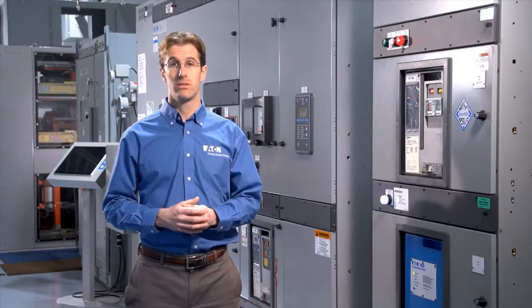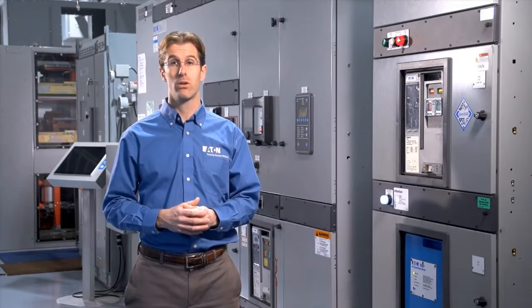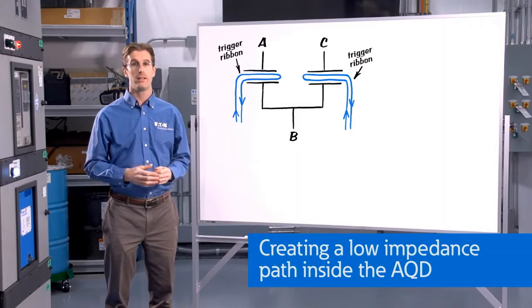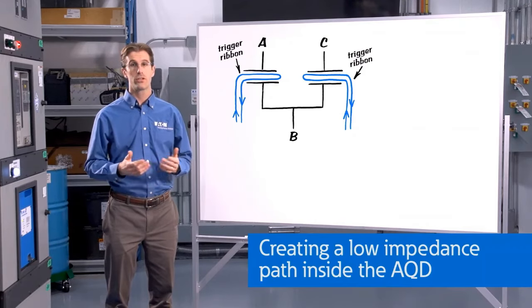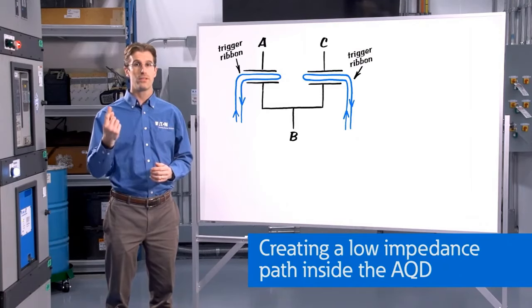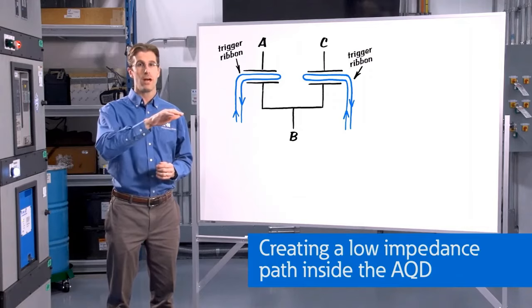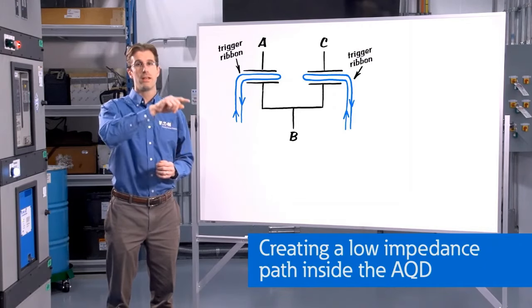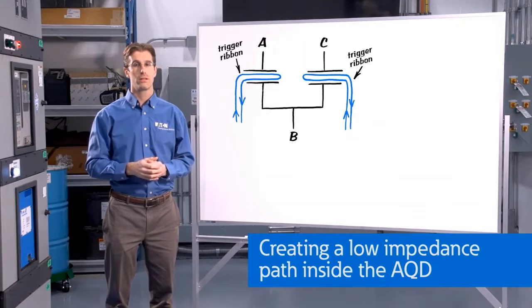But under certain circumstances, we want to be able to create a lower impedance current path inside the arc quenching device in order to extinguish an unintended arcing fault. And the way we do that is by creating a fully contained lower impedance arcing fault inside each arc containment vessel. The arcing fault is created by using a trigger ribbon. It's essentially a wire. The ribbons shown here in blue run up the side of each of the lower contacts, across the top of each contact, down the side, and then they double back on themselves and return to the trigger board. So when we want to create a lower impedance current path to divert the arc energy into the arc quenching device, all we do is pass current through each of the trigger ribbons.